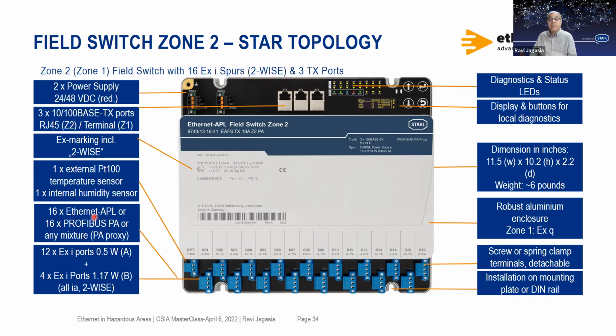The 16 Ethernet APL ports and probably the Profibus PA, and I'll come to that a little later, or any other mixtures. The 12 EXI ports of half watts or 4 EXI ports of 1.17 watts with 2-WISE. Definitely a lot of diagnostics and status LEDs. If you remember, you used to have diagnostics for Profibus PA or FF, where we used to monitor the diagnostics and use either a diagnostic module and then monitor them in the asset manager. You could do diagnostics in the field, and of course it is transmitted over one of the ports available, and then you can transfer the diagnostic data remotely into a control room.